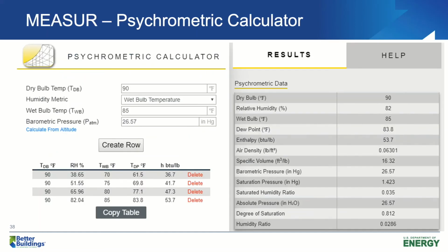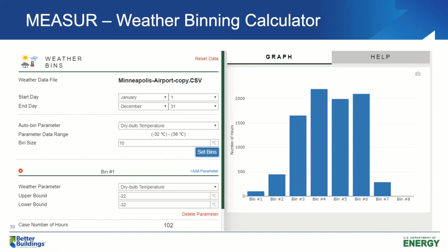Right now, we have 3 process cooling system related calculators in our MEASUR tool suite. The first one is psychrometric calculator. If you have dry bulb temperature, wet bulb temperature, or relative humidity or dew point, this calculator can calculate all other properties of the air for you. For example, you can get enthalpy, air density, specific volume, degree of saturation, and humidity ratio.